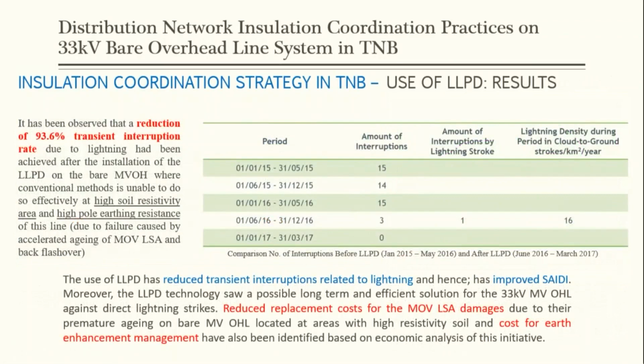And as a result, it has been observed that a reduction of 93.6% in transient interruptions rate due to lightning had been achieved after the installation of the LLPD on the bare medium voltage overhead line, where conventional methods are unable to do so effectively in high soil resistivity areas and high pole earthing resistance on this line, due to failure caused by accelerated aging of the MOV line surge arrestor and back flashovers.